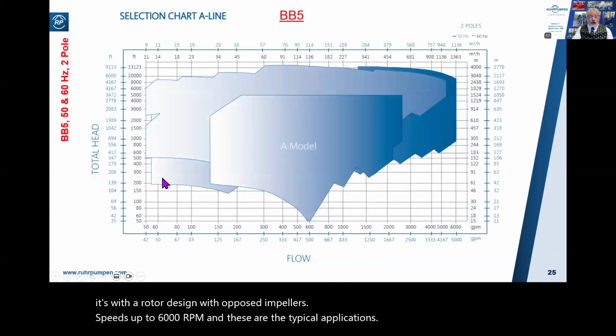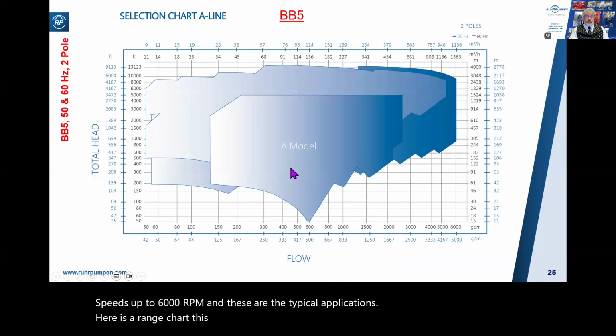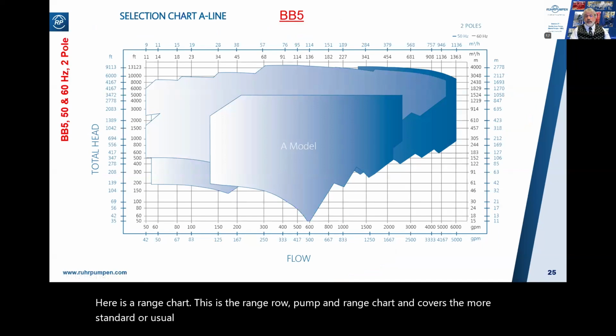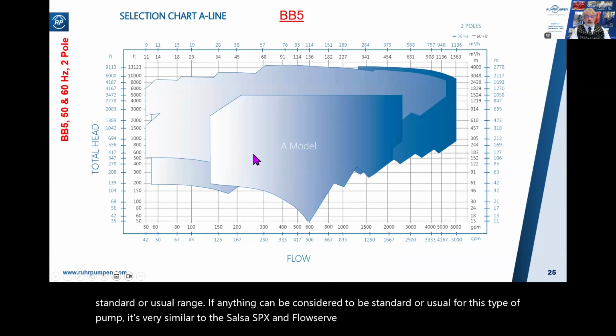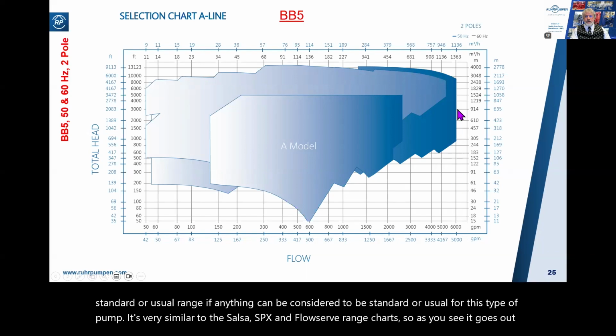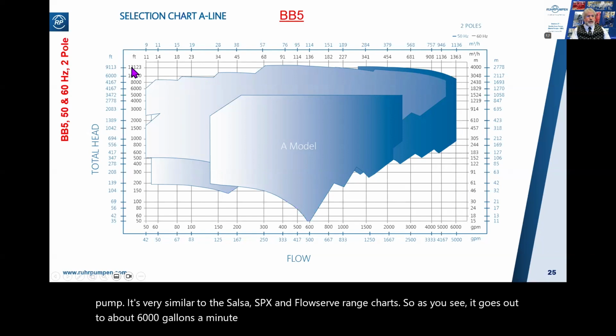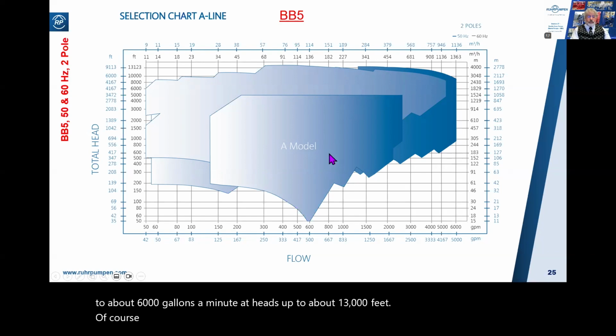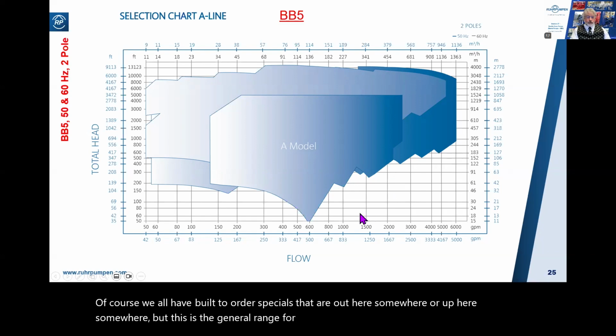Here is a range chart. This is the Ruhrpumpen range chart and covers the more standard or usual range, if anything can be considered to be standard or usual for this type of pump. It's very similar to the Sulzer, SPX and Flowserve range charts. So as you see, it goes out to about 6,000 gallons a minute at heads up to about 13,000 feet. Of course, we all have built-to-order specials that are out here somewhere or up here somewhere. But this is the general range for most manufacturers.